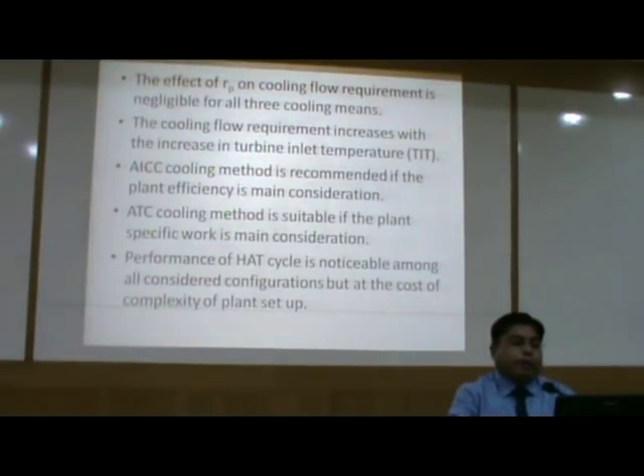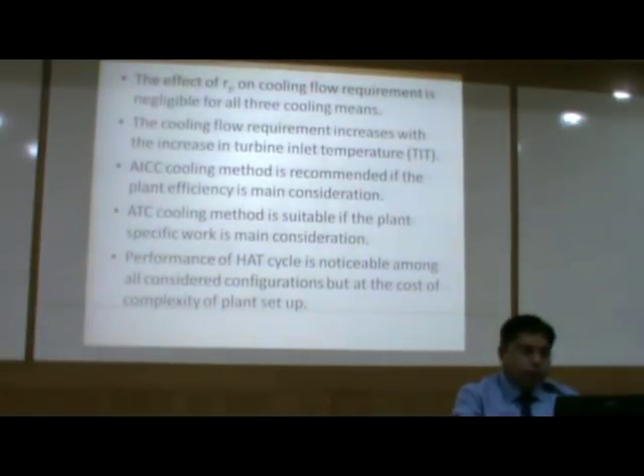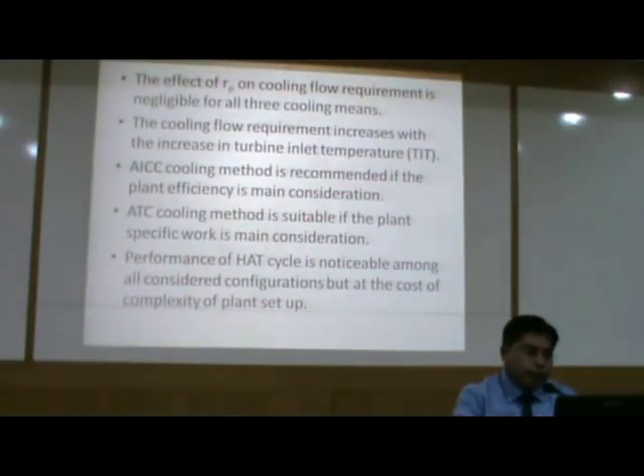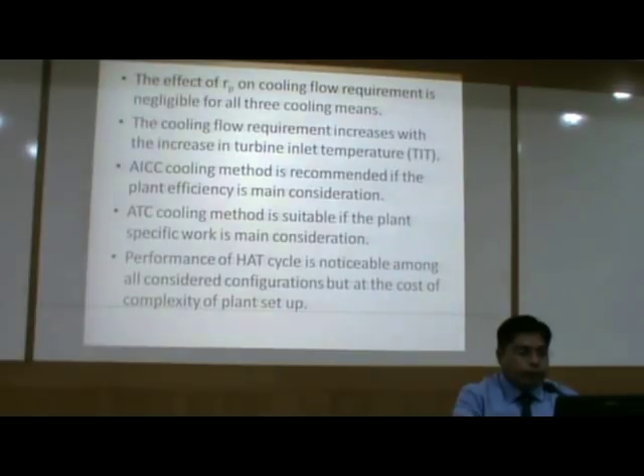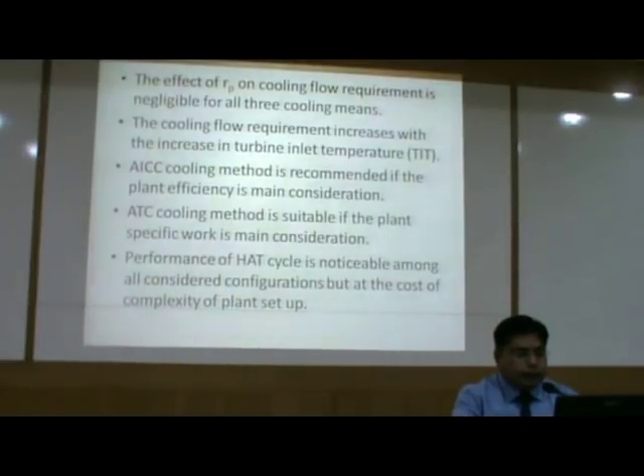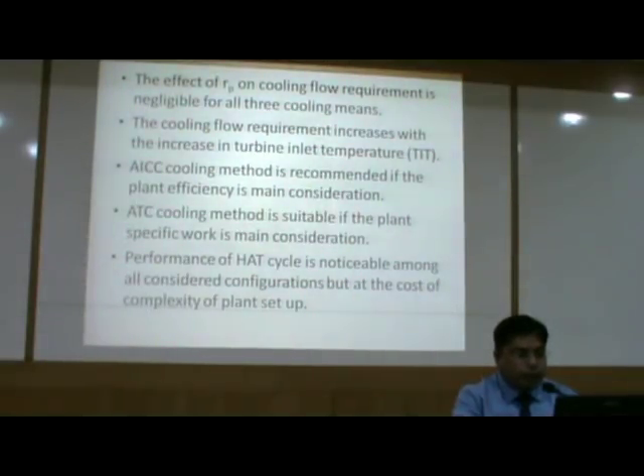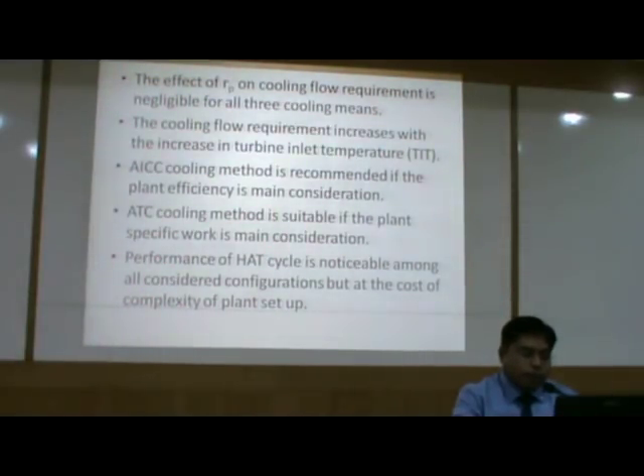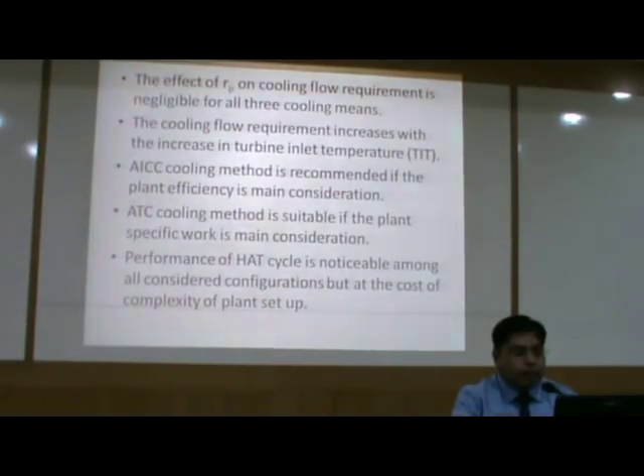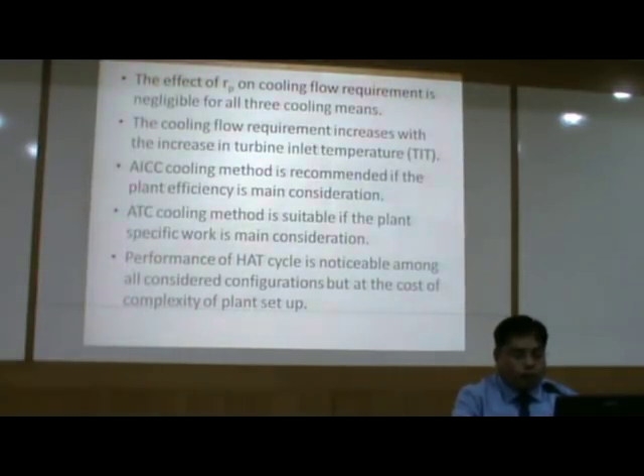The effect of compression pressure ratio on cooling flow requirement is negligible for all three cooling means — AICC, ATC, and AFC — while cooling flow requirement increases with increasing turbine inlet temperature. Regarding cooling means: AICC cooling is recommended if plant efficiency is the main consideration, while transpiration cooling is suitable if specific work is the main consideration. The performance of the humid air turbine (HAT) cycle is noticeable among all the considered configurations, but of course at the cost of complexity of the plant setup.